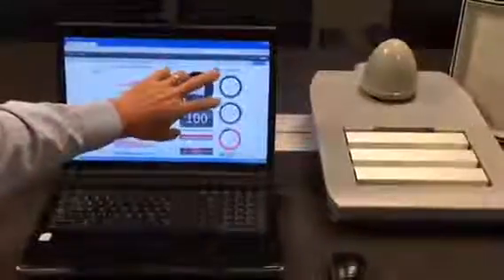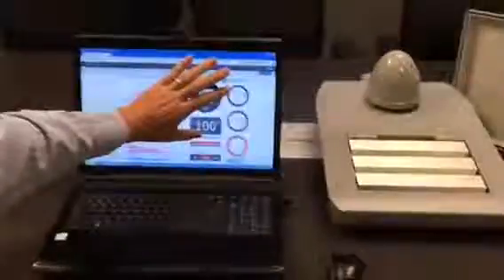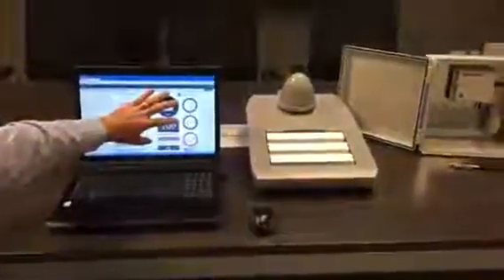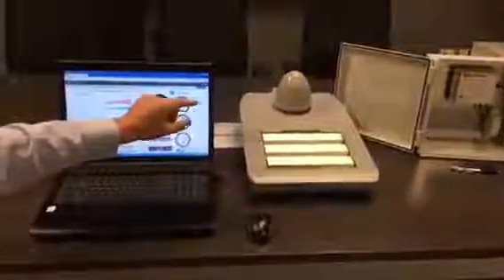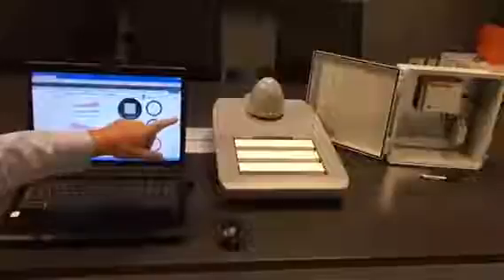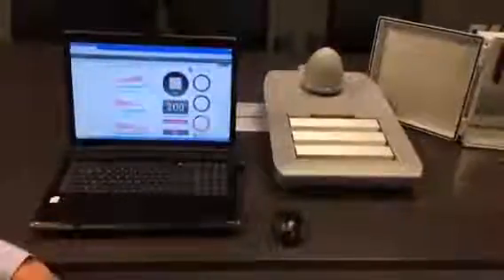Over here we have real-time meters. Again, we have utility grade metering, which is 0.05% accuracy built into the actual node. So it's monitoring the power of every streetlight individually, to utility grade accuracy. We've got amperage shown here, we've got wattage, and we've got voltage, which is 120 volts. This is just a little graphic to show you when it's on.